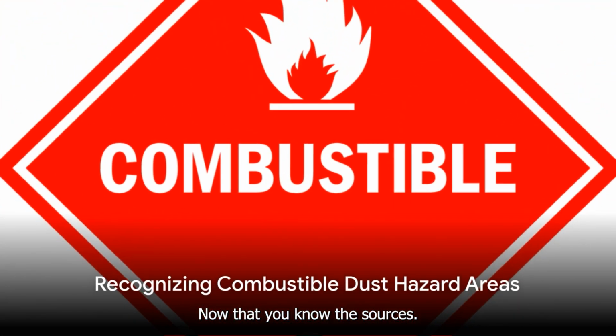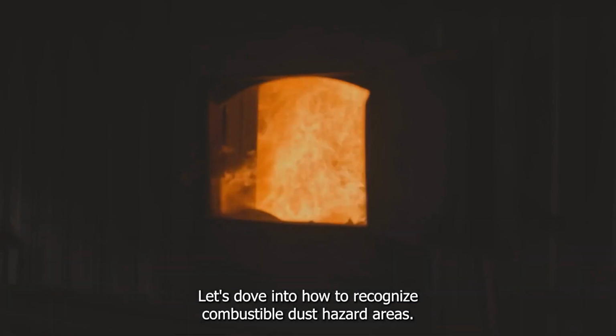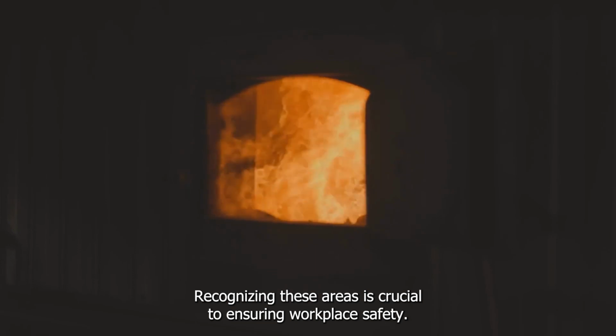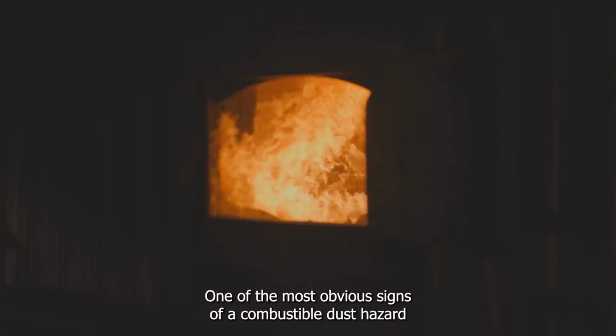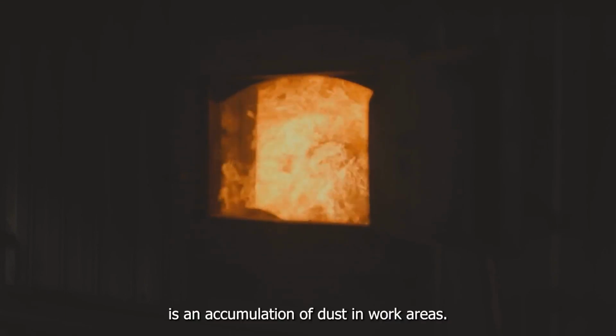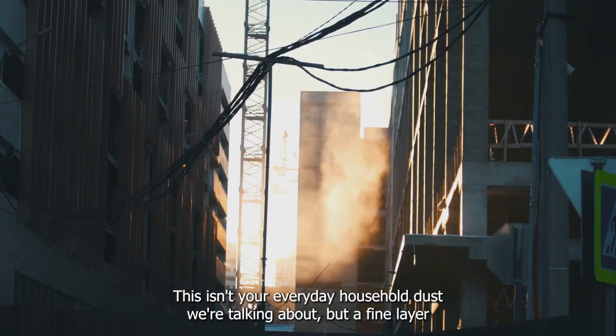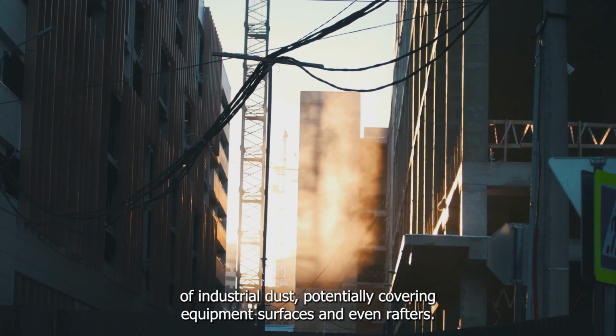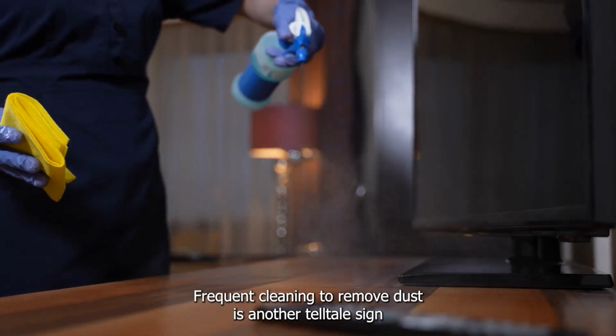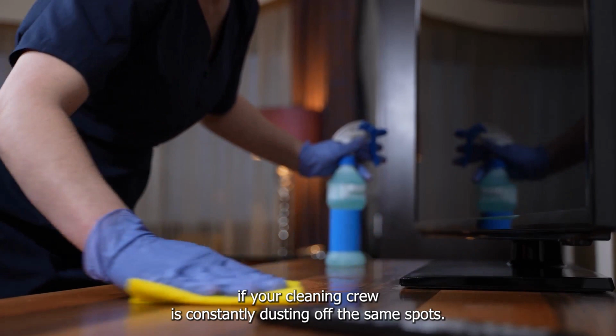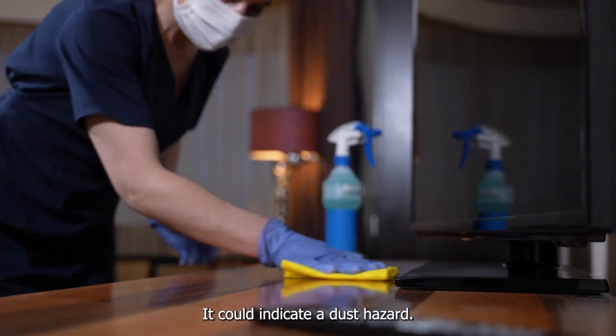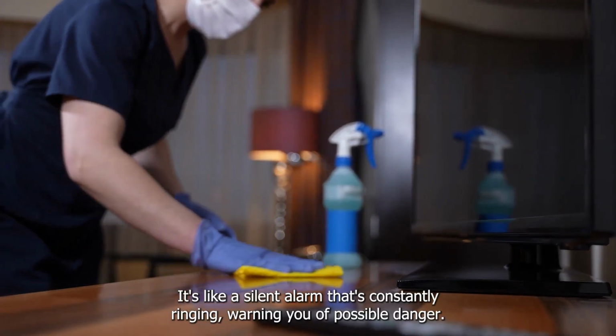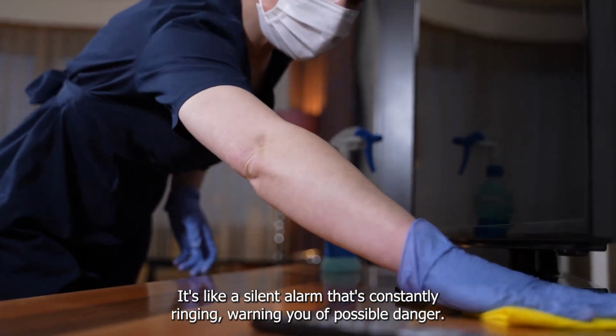Now that you know the sources, let's dive into how to recognize combustible dust hazard areas. Recognizing these areas is crucial to ensuring workplace safety. One of the most obvious signs of a combustible dust hazard is an accumulation of dust in work areas. This isn't your everyday household dust we're talking about, but a fine layer of industrial dust, potentially covering equipment, surfaces, and even rafters. Frequent cleaning to remove dust is another telltale sign. If your cleaning crew is constantly dusting off the same spots, it could indicate a dust hazard. It's like a silent alarm that's constantly ringing, warning you of possible danger.